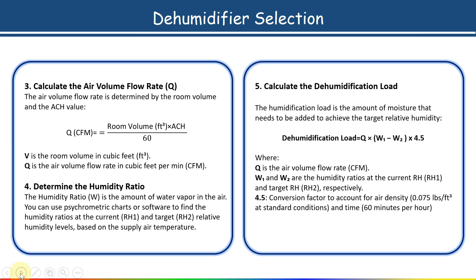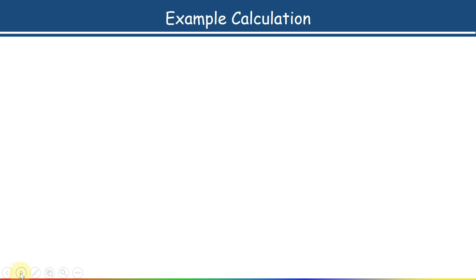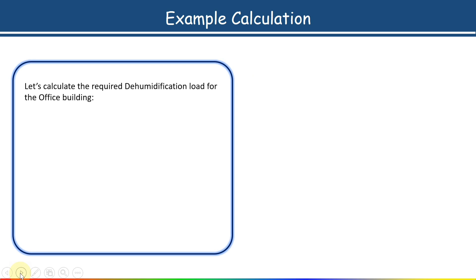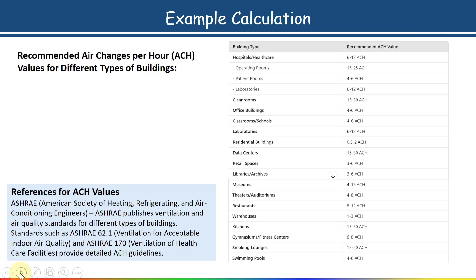Now I will show you an example calculation so you can easily understand how to select and size the dehumidifier. Let us calculate the required dehumidification load for an office building. The room volume is 15,000 cubic feet. The air changes rate for an office building — from the table, the recommended range for office buildings is 4 to 6 air changes per hour, meaning in one hour the air can be changed 4 to 6 times.